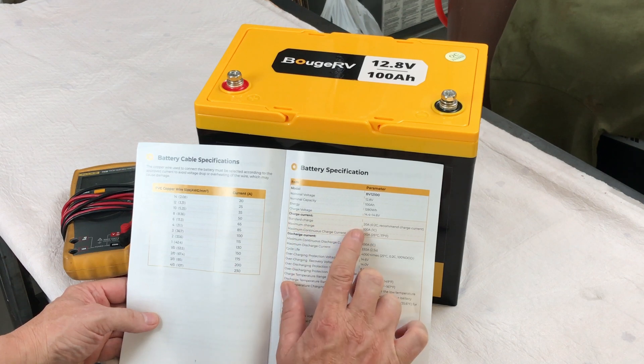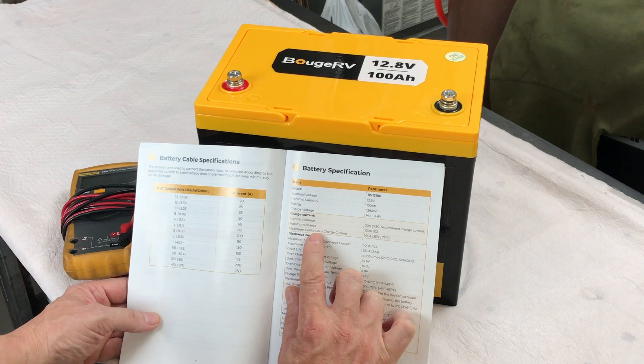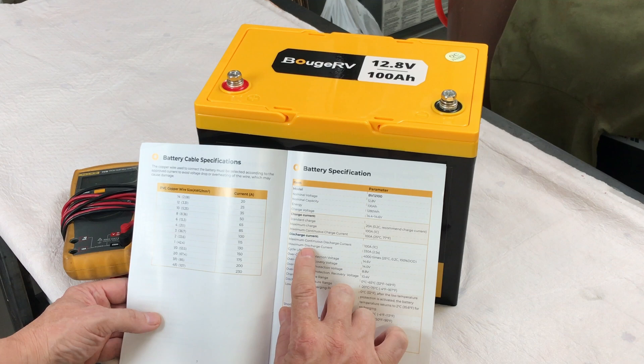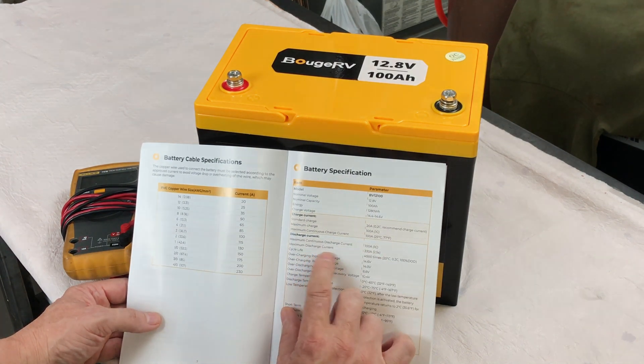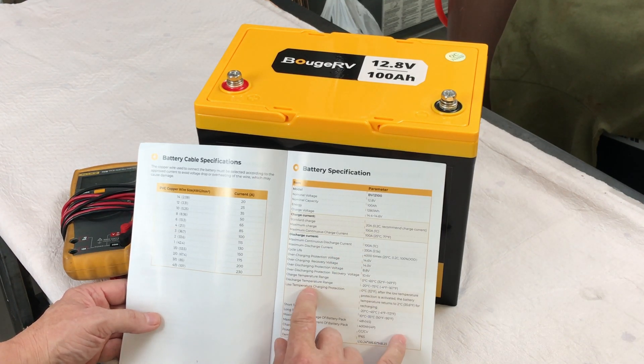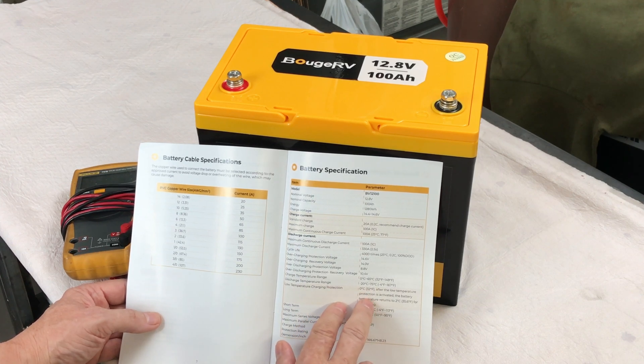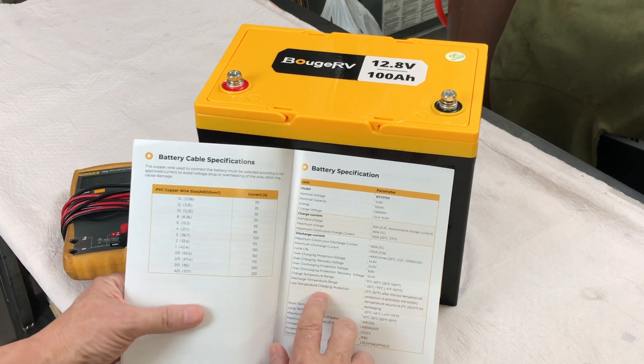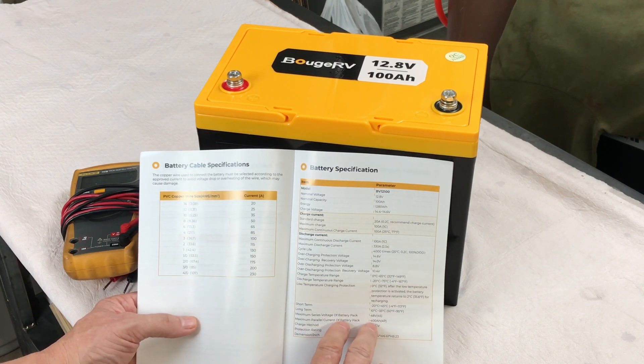Standard charge is 20 amps, maximum charge is 100 amps, maximum continuous charge current 100 amps, and maximum continuous discharge is also 100 amps. Maximum discharge current is 330 amps for two and a half seconds. Cycle life is 4,000 cycles to 100% depth of discharge. Low temperature charge protection activates at 32°F and reactivates as the battery warms to 35.6°F — we'll test that feature out. Maximum series voltage is 48 volts and maximum parallel capacity is 400 amp hours.